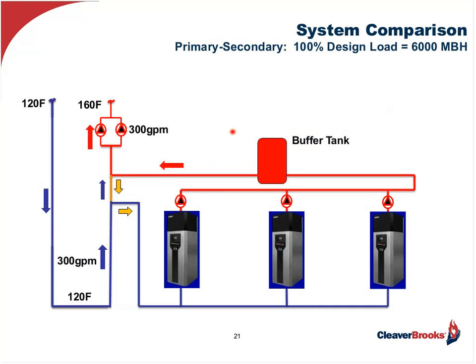We've designed it for 6,000 MBH, 160 degrees out, 120 coming back. The designer used that high delta T in there to minimize its flow. That gives us a flow rate of 300 GPM. We're going to have 3 boiler pumps running, so that's 300 GPM in the primary loop. Because of that, we're going to have absolutely no flow into the coupler. The water is going to come in, go to the boilers, and then go back out to the system without ever passing through to the coupler.